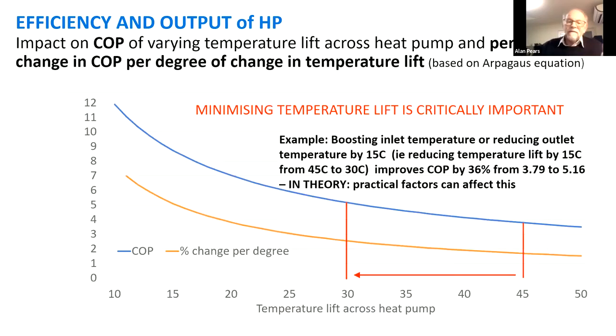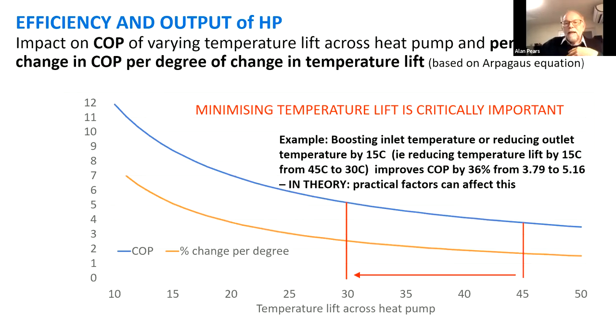When people talk about heat pumps they talk about coefficient of performance, or COP. The COP is essentially the efficiency divided by 100: a 100% efficient electric fan heater has a COP of one. A COP of four means you're being four times as efficient as the most efficient electric heater. This graph highlights the orange line showing the percentage change in COP you get by reducing the temperature lift across the heat pump by one degree, and the temperature difference between the evaporator and condenser is incredibly important.